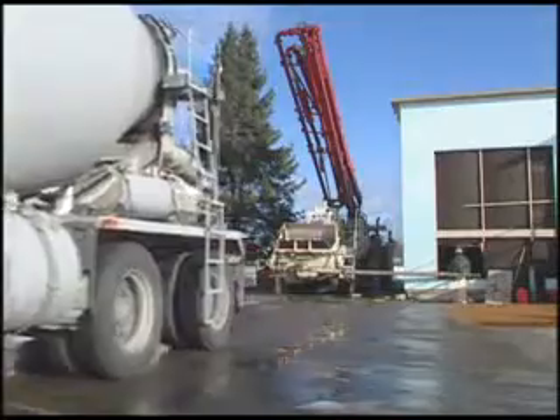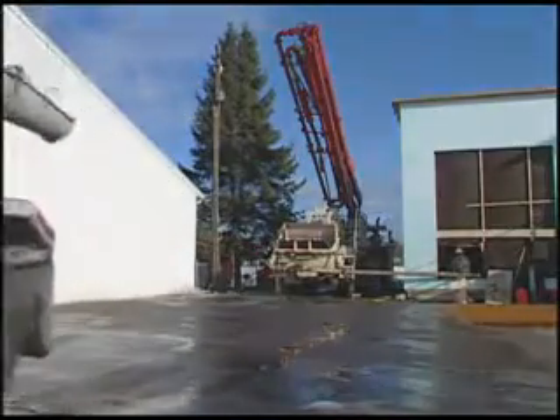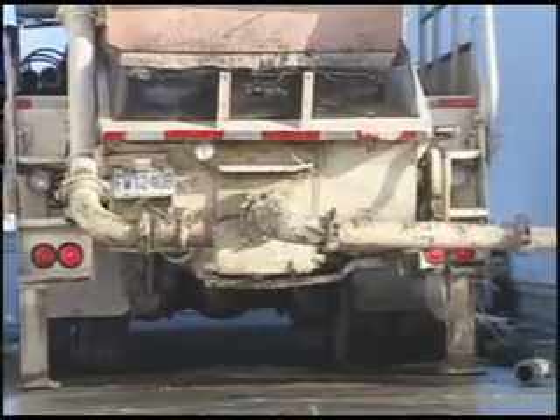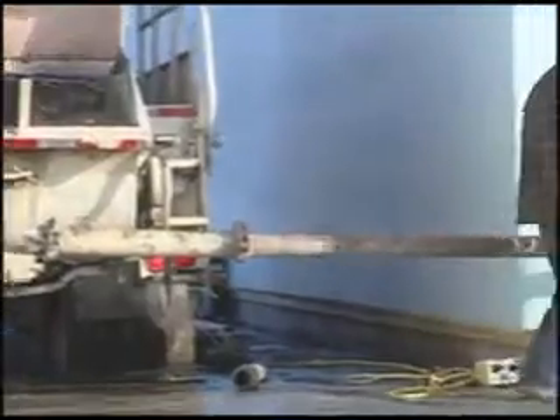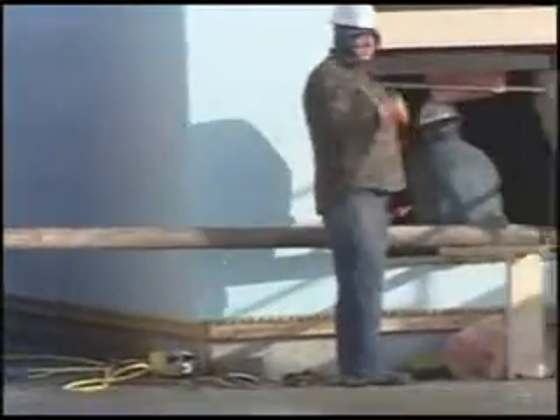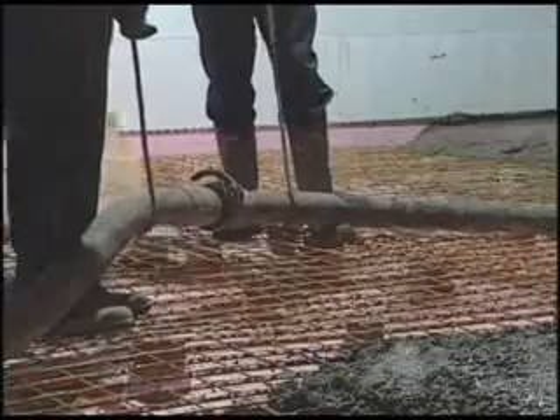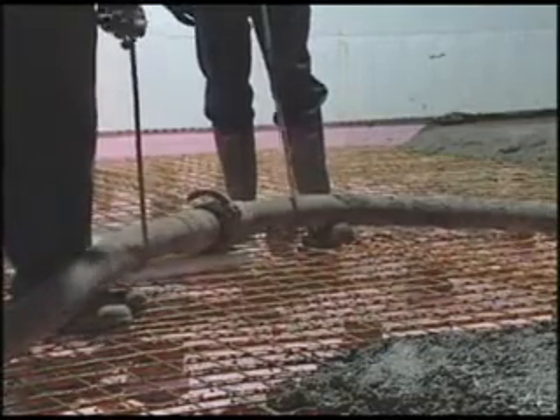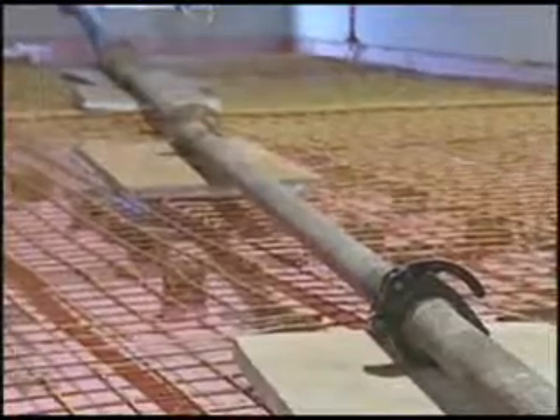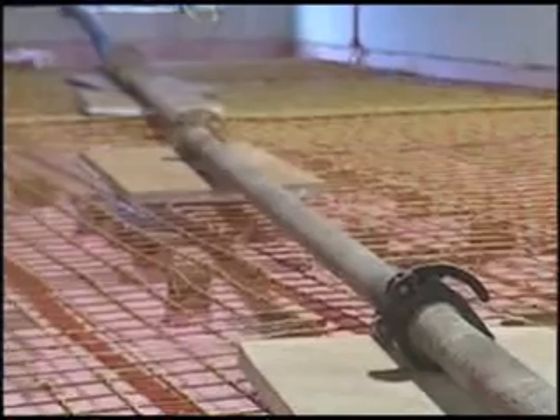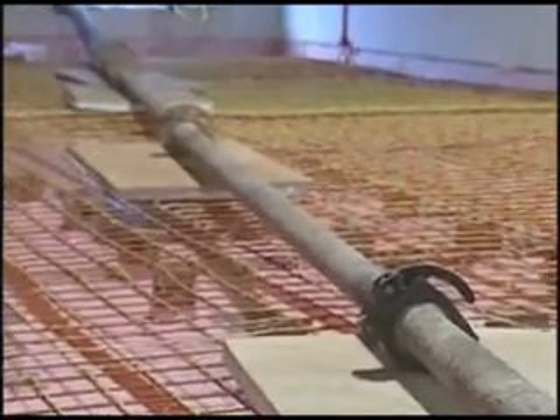Certain precautions must be observed to prevent damage to the cables. Use only a concrete pump to pour material where it is needed. In order to avoid any harmful contact between the pour pipe and the cables, have on hand a sufficient number of protective polystyrene foam panels with plywood backing. The pipe's connecting joints will rest on these panels and will not harm the cables.